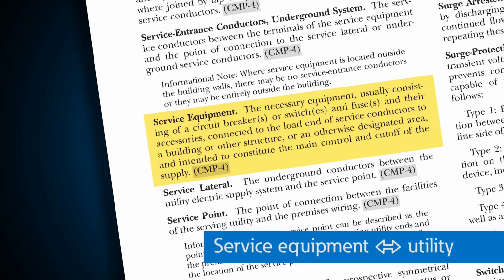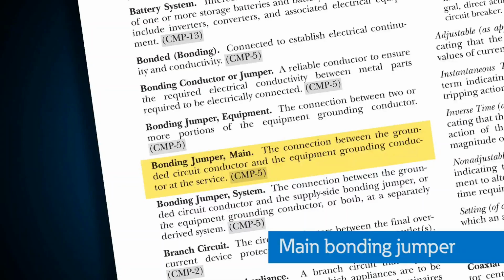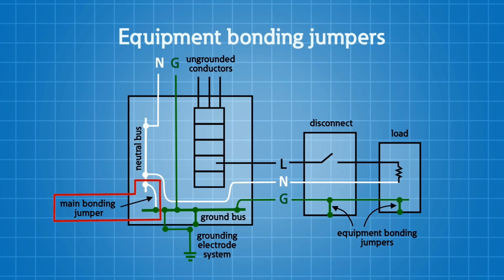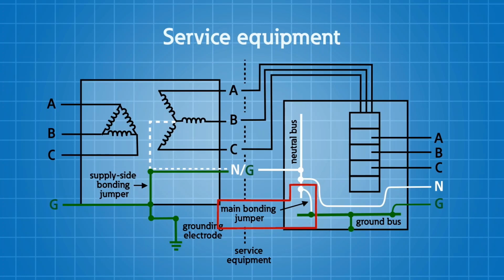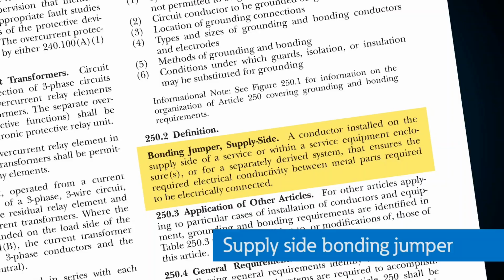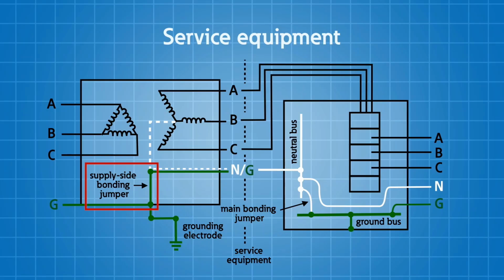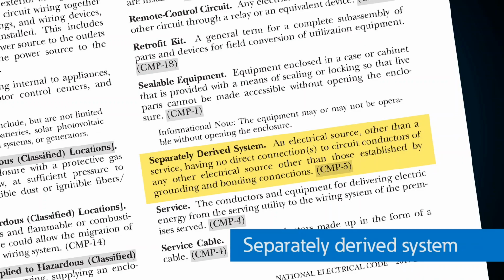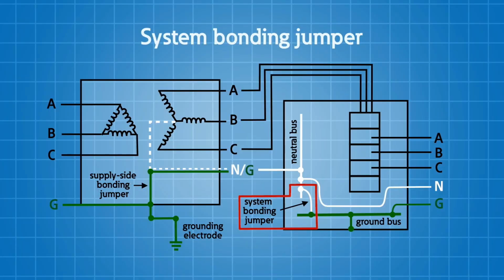Your service equipment, so when we get into service equipment, this is where your utility is connecting into the power distribution system. And in this equipment is where we're going to find some very important bonding jumpers. One of those is the main bonding jumper: the connection between the grounded circuit conductor and the equipment grounding conductor, or the supply side bonding jumper, or both, at the service. So this is your main bonding jumper, that point where we pull both of those conductors or those systems together. Now your supply side bonding jumper is the conductor that's installed on the supply side of the service or within the service equipment enclosures, or for a separately derived system, that ensures the required electrical conductivity between the metal parts that are all required to be electrically connected.